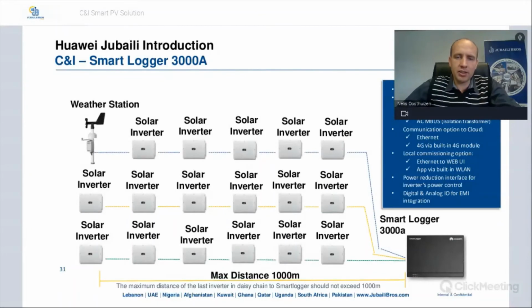This next diagram is basically just showing you how you would be setting up the communication between the inverters on a Smart Logger 3000A. So the first green line would be a first string of inverters. As I've mentioned, up to a maximum of 30 can be daisy chained. And then the second one is the yellow one, also again up to 30. Maximum distance between the logger and your last inverter in the string is 1000 meters. Then if you do have a weather station, please make sure that it's the last one in the specific string. So don't connect it first in the string and then daisy chain the inverters to that one. It should be the last in your daisy chain.